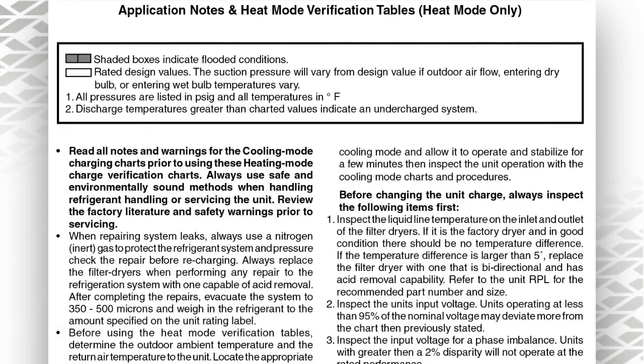In the installation instructions, we reference discharge temperature in the heating mode. Remember, as I spoke to you a minute ago, where your high side gauge is hooking up to that unit, that is your discharge line. Now the installation instructions refer to the discharge line being right off the compressor inside the unit. But I don't know that I'd even go in there unless I absolutely have to. I'd go to the discharge line outside the unit, same place I got my gauge hooked up, and verify the operation of the unit. As long as I'm within a few degrees of that discharge temperature, then I know I'm okay.